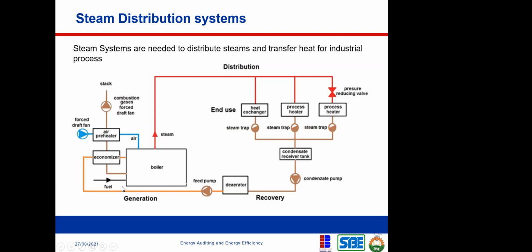into the boiler. But before we send it into the boiler, you will see that it passes through an economizer. I remember I explained what an economizer is. That water passes through the exhaust pipe of the burner so that it can also acquire some of the heat in the exhaust before it goes into the boiler. So you don't need so much heat to raise that water to 100 degrees centigrade. Right? So this is how you save energy in a boiler and steam system. One is that you don't throw away the condensate. Two is that you have to recover the exhaust heat from the exhaust pipe through either an economizer or a recuperator. These things should stand out.